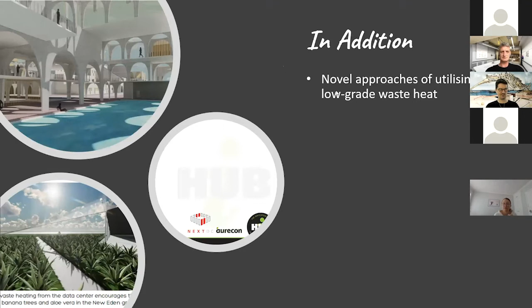In addition, we also saw some novel approaches to utilizing low-grade waste heat. There was an idea of using thermal energy exchange within greenhouses and publicly accessible swimming pools, which in turn would reduce loads on the chillers of the facility and the cooling towers, meaning the cooling towers could be smaller or tend to operate in a more efficient manner.